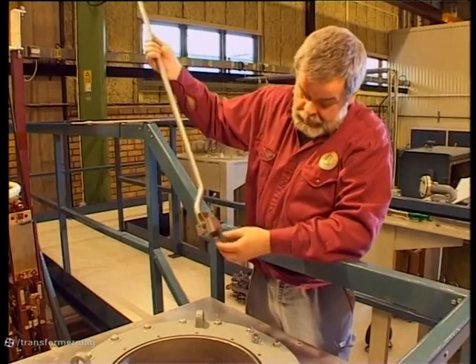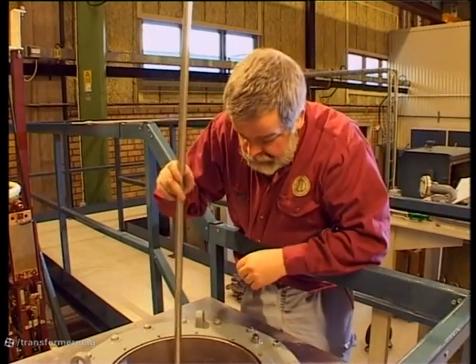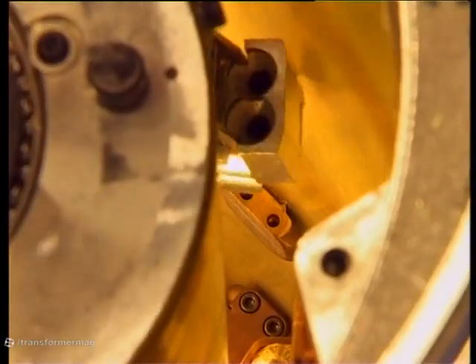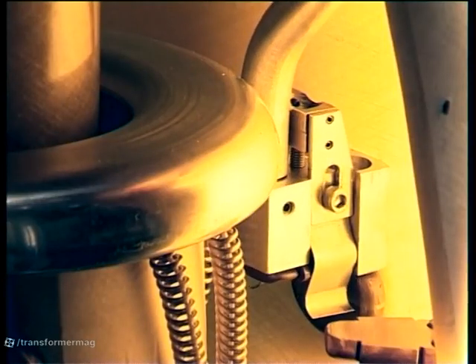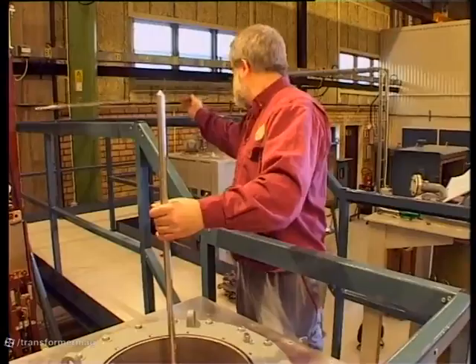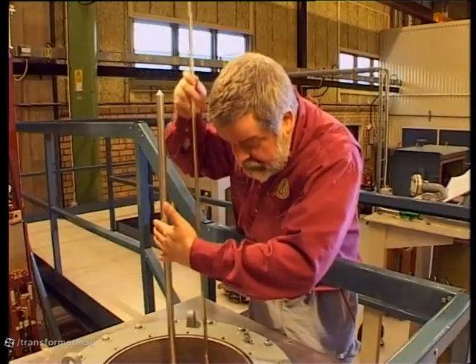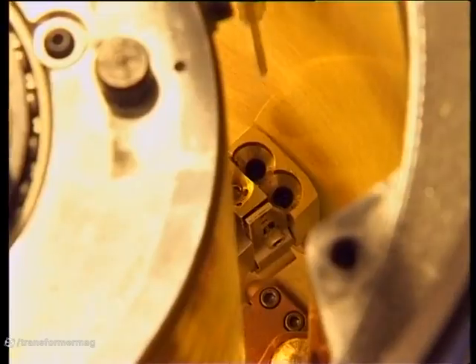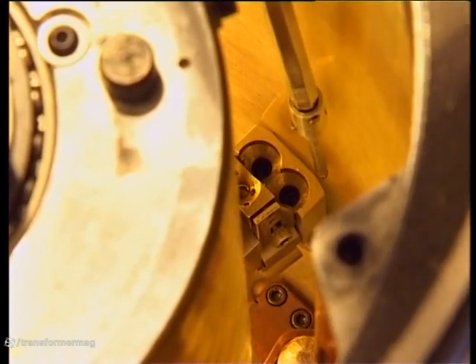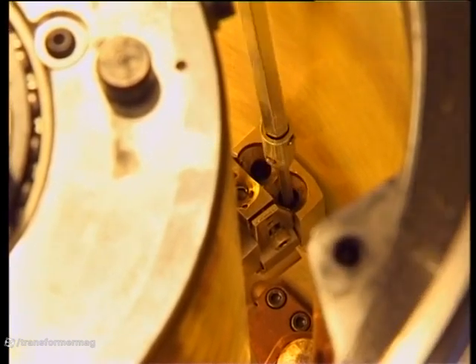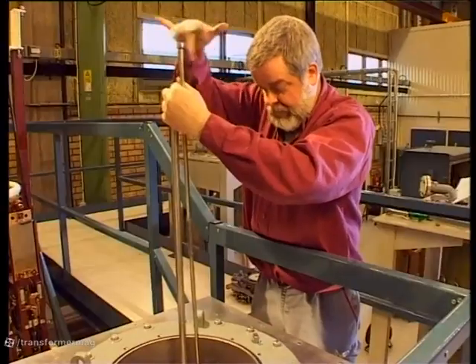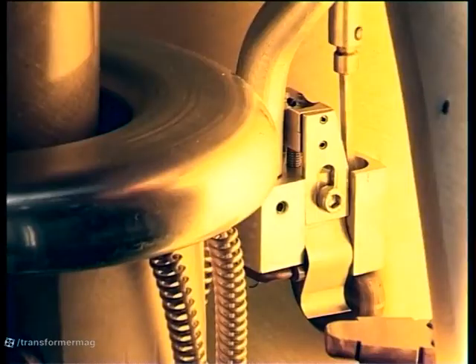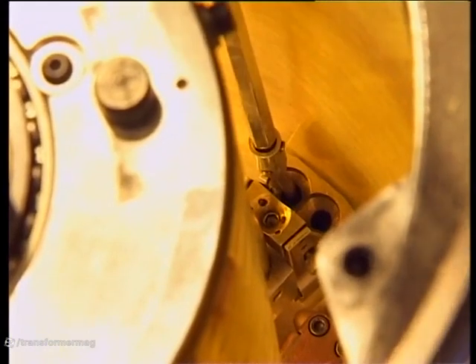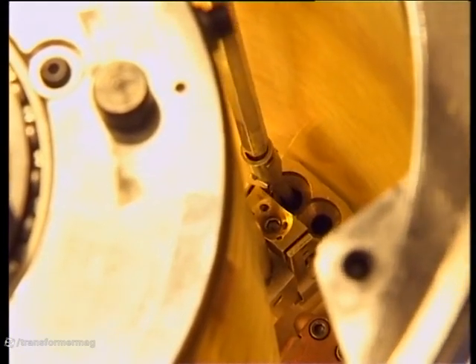Now, we're in the studio again. You're now going to use the contact tool and the screwing tool. This may look trickier than it is in reality. The screws are guided into the threads by countersunk holes. The tightening torque is 12 Newton meters. Use a torque wrench to be sure that the torque is correct.